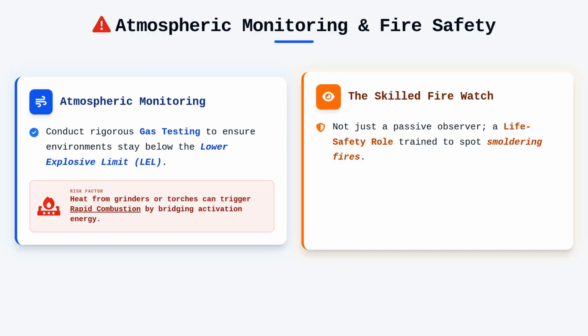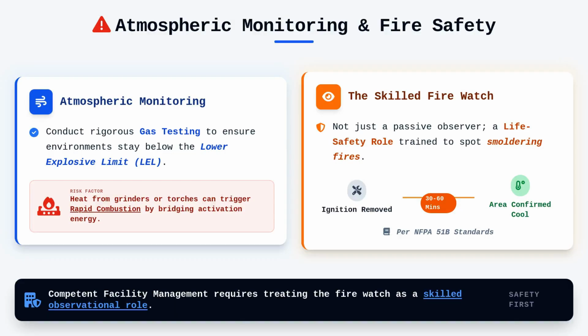Furthermore, the fire watch plays a life safety role that extends beyond simply having a fire extinguisher on hand and ready for use. This person must be explicitly trained to identify smoldering fires that may remain unnoticed for an extended time after the work is deemed complete. NFPA 51B recognizes that this period of observation is critical, often requiring a fire watch for at least 30 to 60 minutes after the source of ignition has been removed. By maintaining a constant presence until the area is confirmed cool, we mitigate the risk of delayed ignition that leads to structural fire loss. Treating the fire watch as a skilled observational role rather than a passive observer is a core requirement of competent facility management.